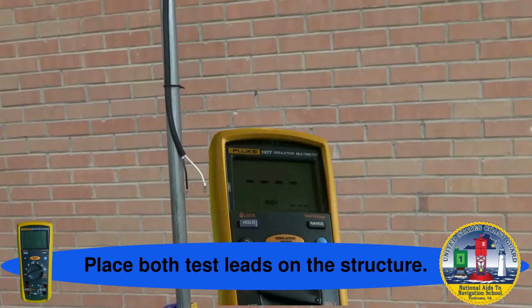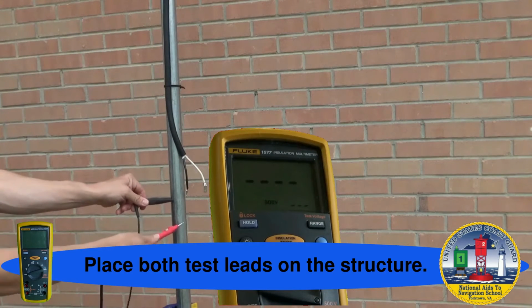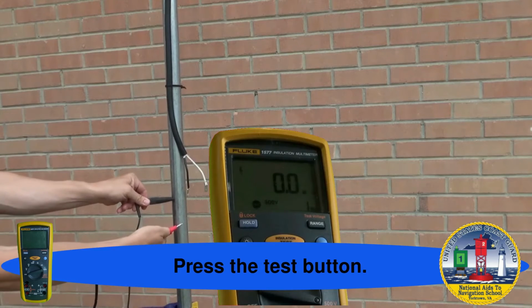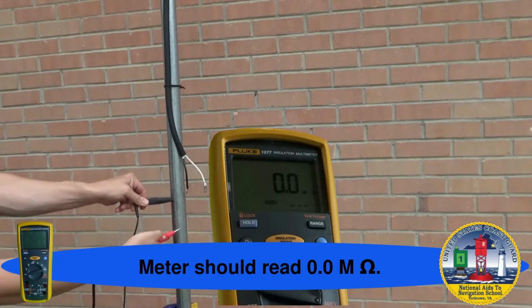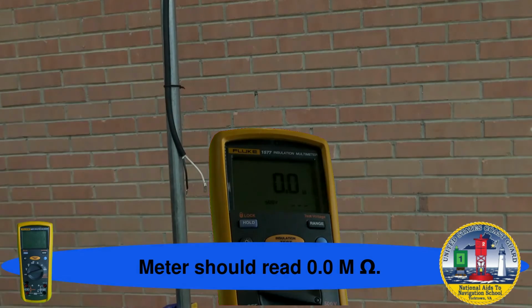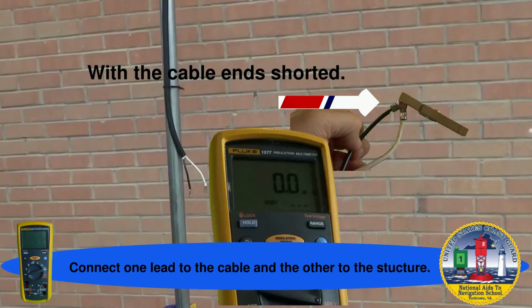Now test to ensure the cable is not shorted to the structure. Place both test leads on the structure and press the test button. You should read no resistance. This is to ensure you have a good contact with the structure. If not, you may have to remove corrosion for a good test point.